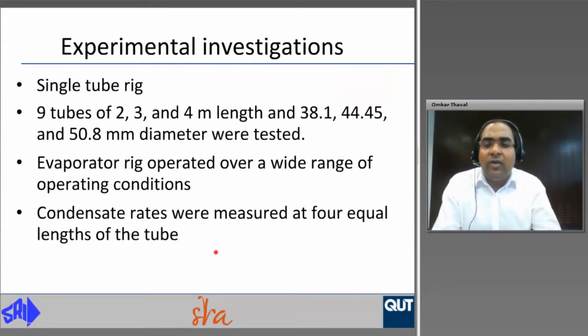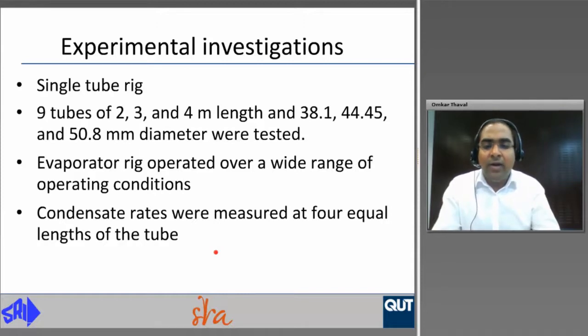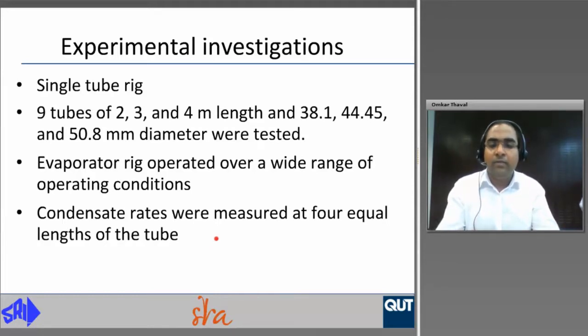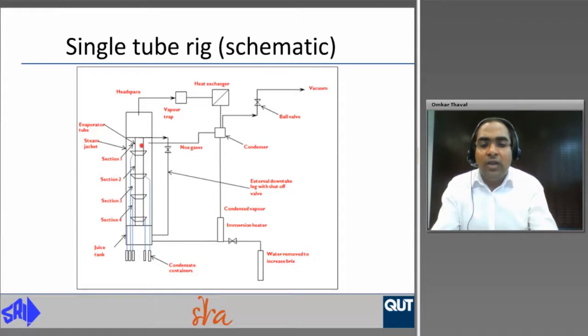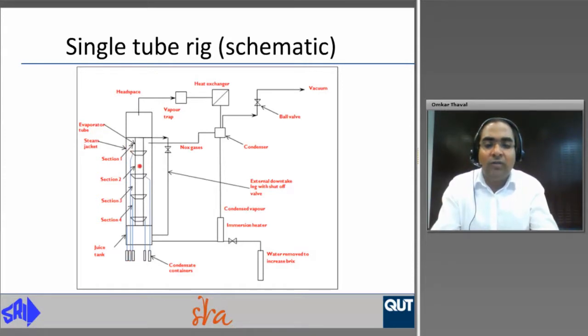The experimental investigation was undertaken for a single tube evaporator rig. Nine tubes of 2, 3, and 4 meter length and 38.1, 44.45, and 50.8 millimeter diameter were tested over a wide range of operating conditions typically encountered in factory vessels. Condensate rates were measured at four equal lengths of the tube. The figure shows a schematic diagram of the single tube rig, where the evaporator tube is encased in a steam jacket and four gutters are placed equidistant along the tube length to collect condensate from each section into containers placed at the bottom.